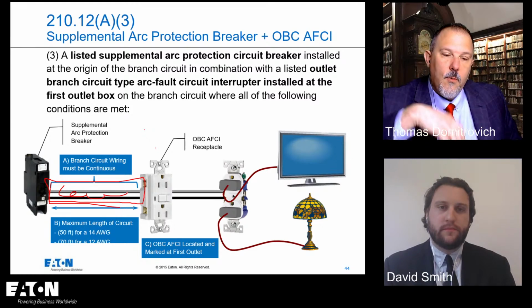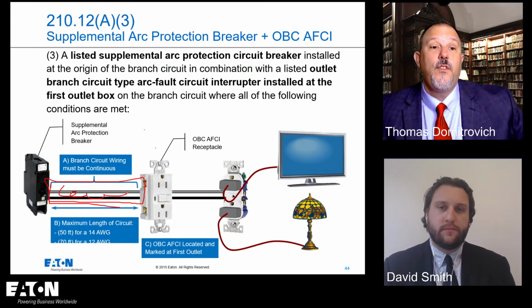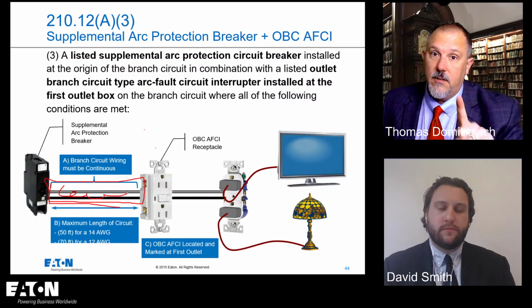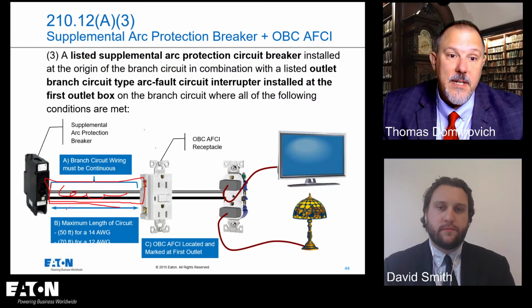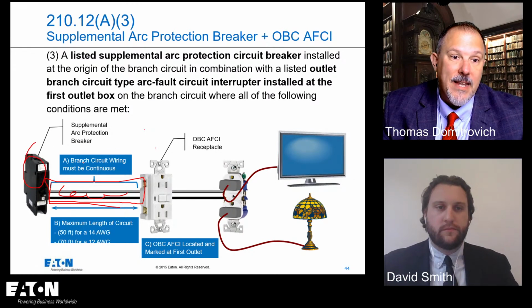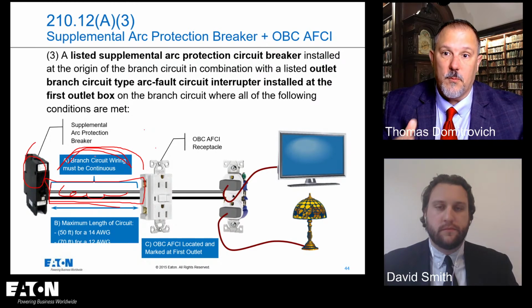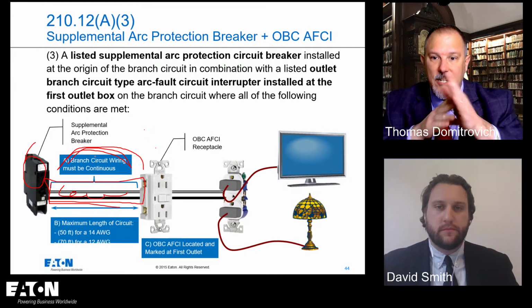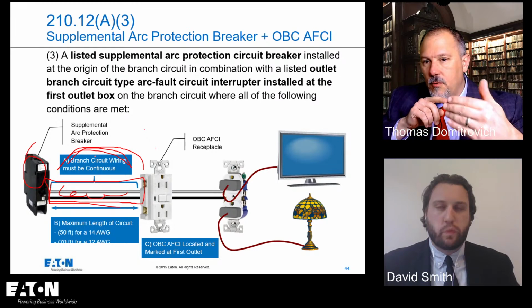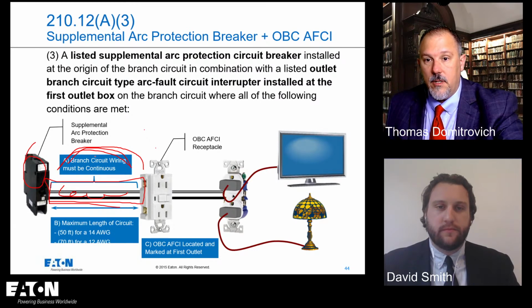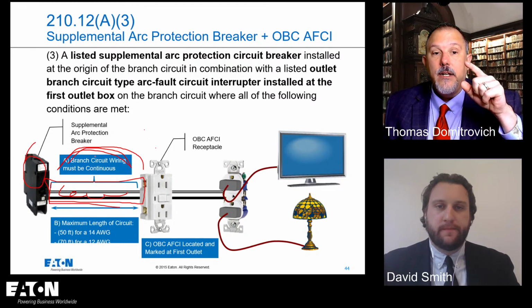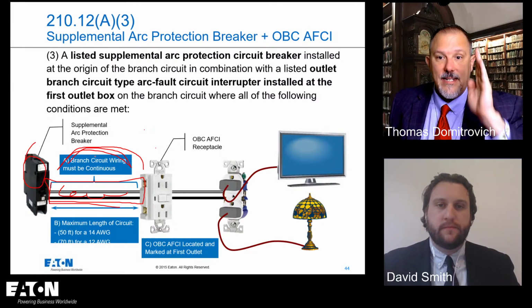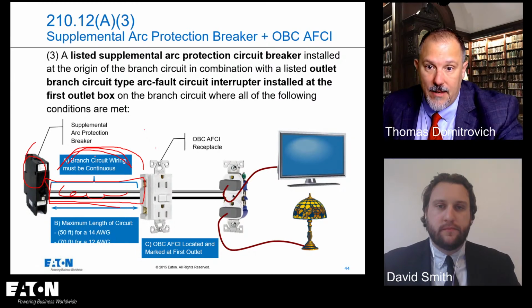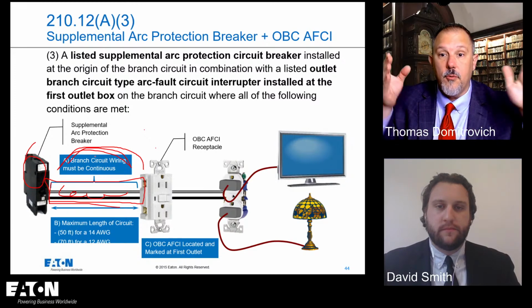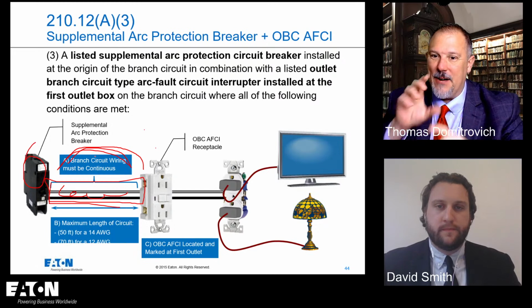So what the wiring device manufacturers were coming to the table saying, hey, look, if you have an arc in that home run circuit, a parallel arc, because that's the only thing, because the OBC AFCI, which we didn't talk about yet, basically does everything that this breaker does, except it can't provide parallel arc protection of this home run circuit. And we could debate on whether or not you can provide series arc protection, because think about it. The way the OBC works is a series arc will, because current's flowing through the damaged series conductor, through the receptacle down to the load, that receptacle will see that waveform. Right. And the receptacle doesn't know if it was downstream or upstream, but it knows I see a bad arc and it can open. And if it's the first outlet, then it's isolating and stopping the flow of current through a damaged conductor.